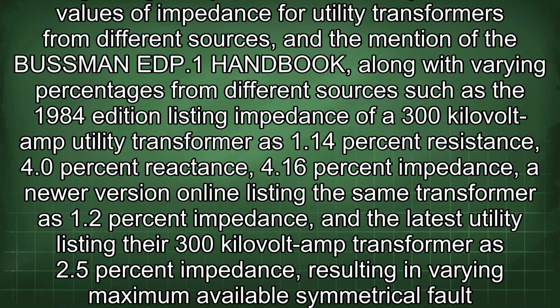Regarding the question about wildly different values of impedance for utility transformers from different sources, and the mention of the Bussmann EDP-1 handbook, along with varying percentages from different sources: the 1984 edition lists the impedance of a 300 kVA utility transformer as 1.14% resistance, 4.0% reactance, and 4.16% impedance; a newer version online lists the same transformer as 1.2% impedance; and the latest utility lists the 300 kVA transformer as 2.5% impedance, resulting in varying maximum available symmetrical fault current between 8,600 and 30,000 amps.